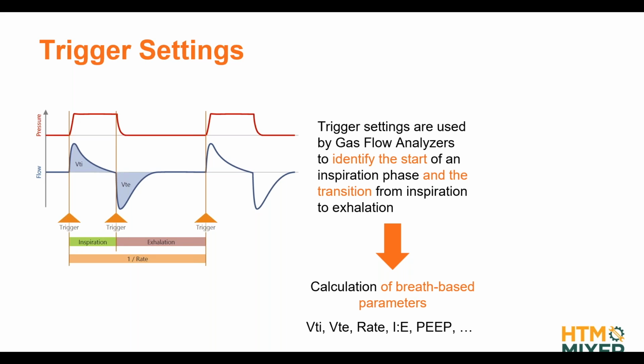So you will hear terms like start trigger and stop trigger, or sometimes also called end trigger. This relates to the inspiration phase. The start trigger marks the start of an inspiration phase, and the stop trigger then marks the end of the inspiration phase, which is also the transition to exhalation. And then the next start trigger means the next breath phase actually starts. And if we know that in our gas flow analyzers, then we can calculate all the different things.